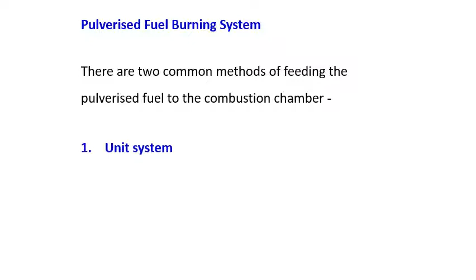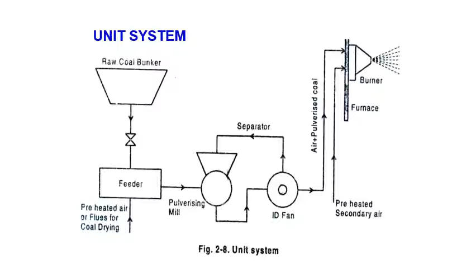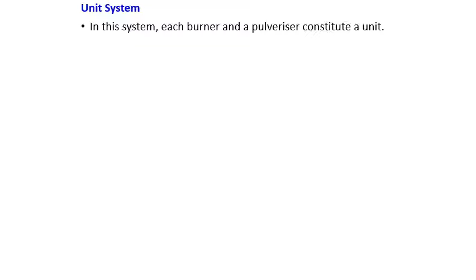The pulverized fuel systems are of two types. First one is called the unit system, second one is called the central or bin system. In the unit system, we have a coal bunker, feeder and a pulverizing mill, and the feeder and this mill along with one burner, that's why it is called a single system. We don't have many burners to the furnace from a single feeder. So here in the unit system each burner of the pulverized fuel constitutes a unit. It consists of a raw coal bunker, a feeder, pulverizing mill, separator and a burner.